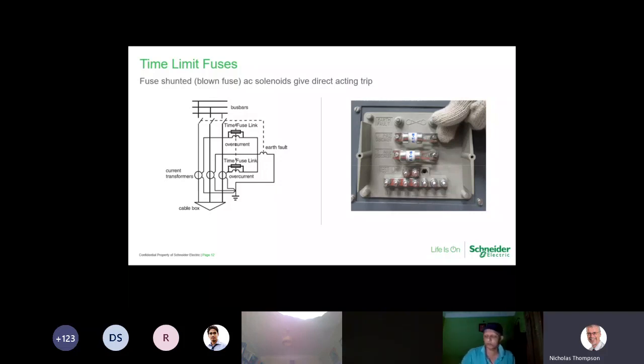You see on the picture on the right hand side there, the fuses are really small. They're not as small as a 13 amp fuse, and they don't look anything like a 13 amp fuse, but we've got various different sizes. Just to explain what we've got on here, we've got our earth fault pins there. So if the consultant or the protection engineer decides he needs to increase the fault current on earth fault, then we'll fit a fuse to cover that. Down here we've got shorting links for our CTs, because it's standard to fit dual ratio CTs for this type of protection. I'm going to come on to that one on the next slide.